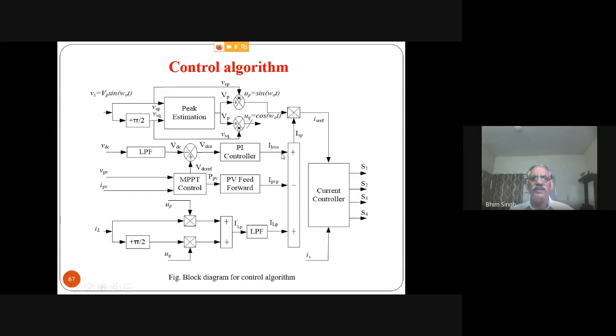It's a notional concept that power should come from the grid, like an active filter concept. Another component is what we get from load current, the fundamental active component, and that also should come from the grid, so we take a positive convention. If solar generation is not there, it should work as an active filter, so you must have some active power for the losses as well as to feed the load, as far as the grid side is concerned.